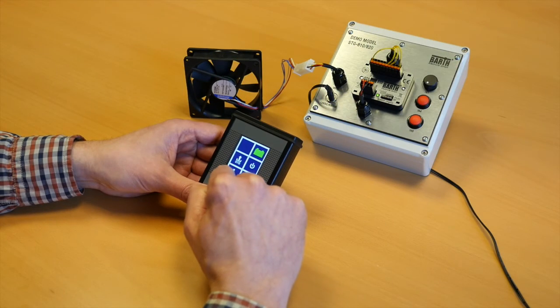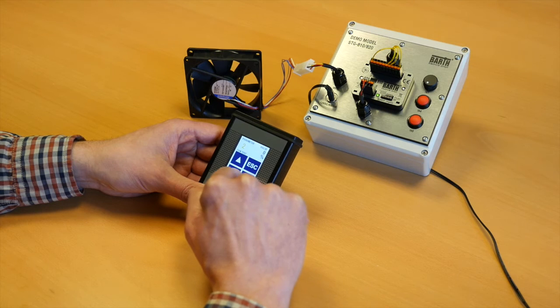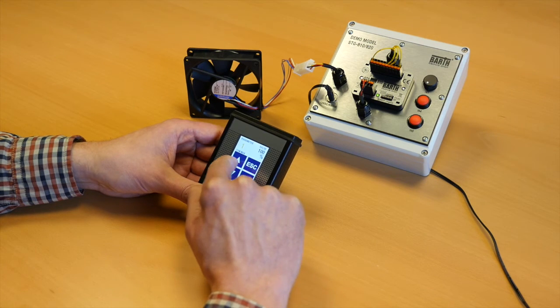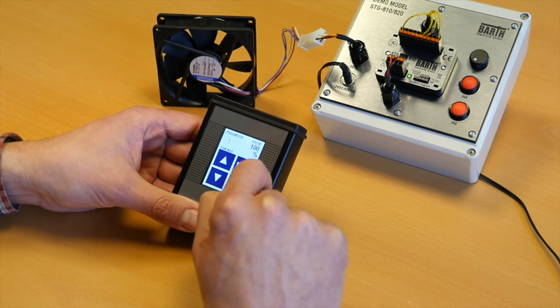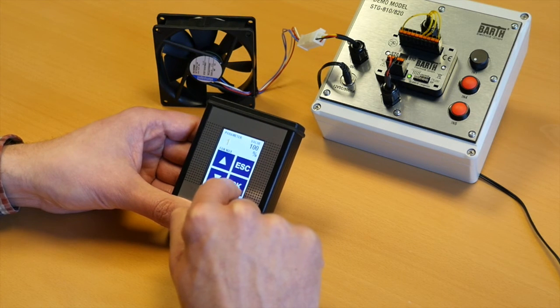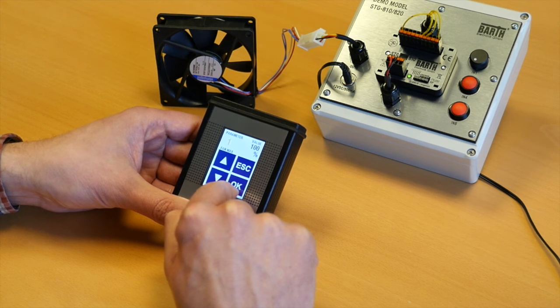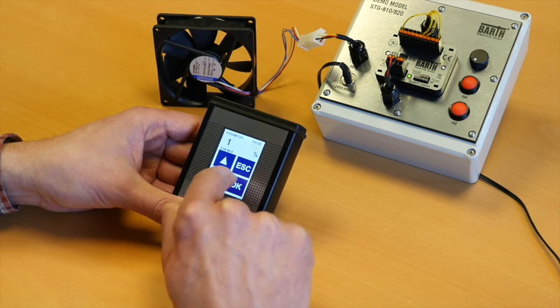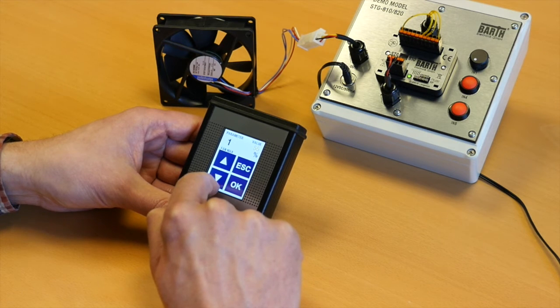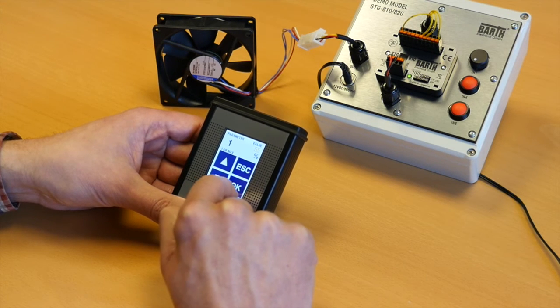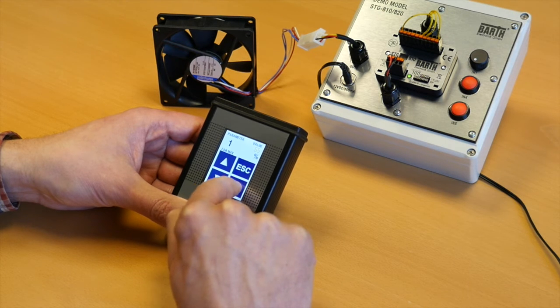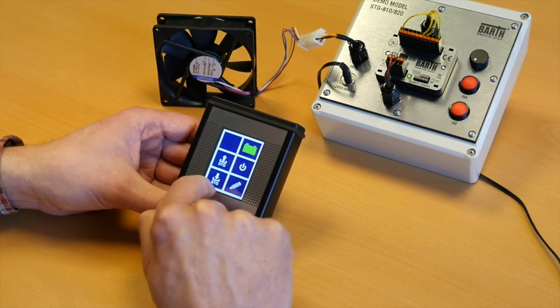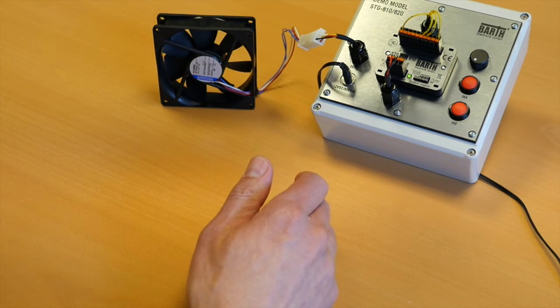In the second step, I'm able to define the maximum fan speed. As standard, the maximum fan speed is set to 100%. To change the maximum fan speed, simply press OK to edit this value. For example, reduce this maximum fan speed to 55%, confirm this with OK, press escape and download it to the mini PLC.